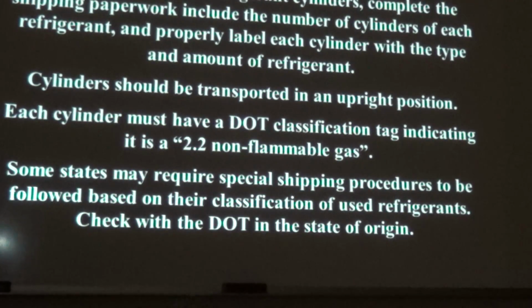Shipping and transportation. Almost all of our refrigerants are going to be 2.2 non-flammable gas. They will not support a flame. We can burn them, but the second we take the flame away, it stops burning. So before you can ship them, you need to have some paperwork. The cylinder needs to be labeled with what is inside the cylinder. The cylinder should be transported in the upright position. The stem should be up. They need to have a DOT classification tag indicating that it's a non-flammable gas. And in New York State, it should also be chained. It needs to be chained.